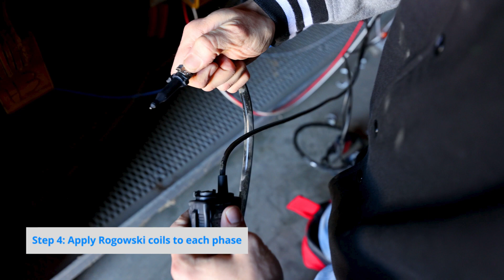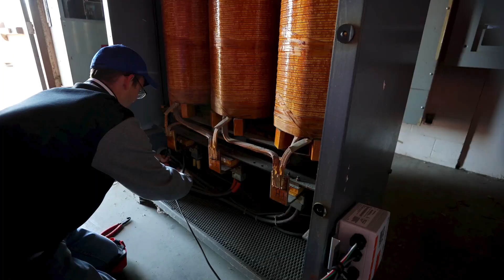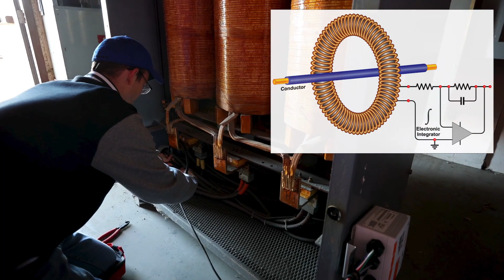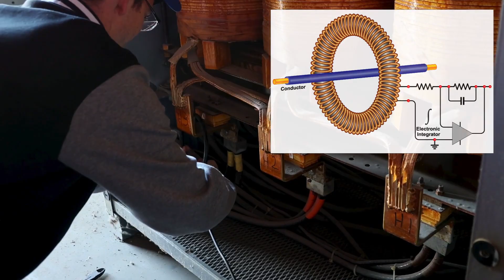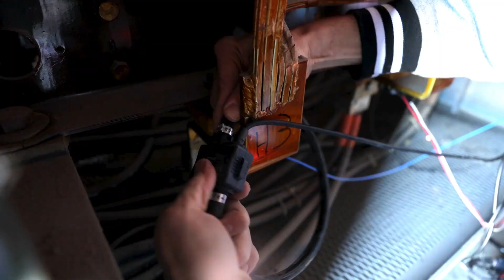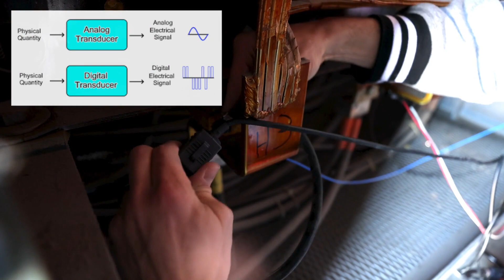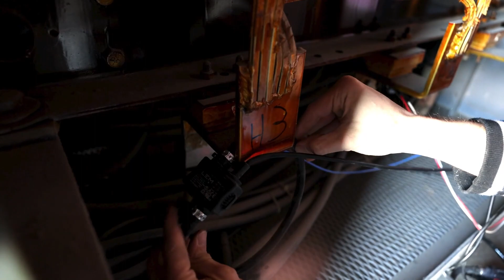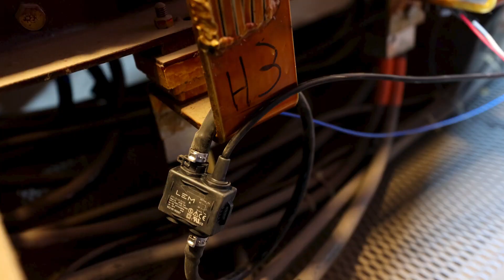This is a special type of coil called a Rogowski coil. Rather than transferring big current to small current, it is actually using an integrator to change big current to small voltage, which will be then transduced by the transformer monitor. It's kind of like a bracelet. You take it apart, twist it apart, wrap it around the bus bar, and then reinsert it and twist it back in place and make sure the arrow is pointing the right direction.